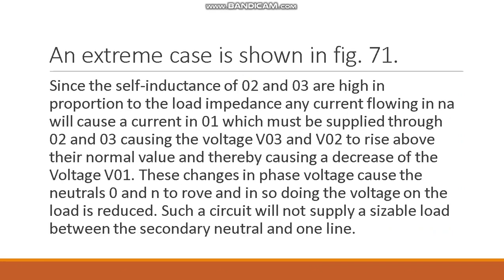Any currents in transformers 2 and 3 must therefore be exciting currents only. Since the self-inductance of 2 and 3 are high in proportion to the load impedance, any current flowing in NA will cause a current IN1 which must be supplied through 2 and 3, causing the voltages V3 and V2 to rise above their normal value, and thereby causing the decrease in voltage V1.